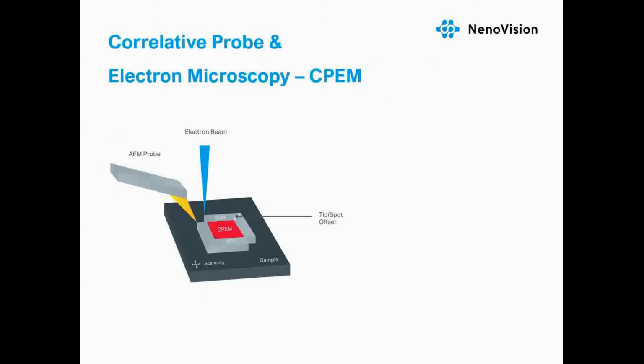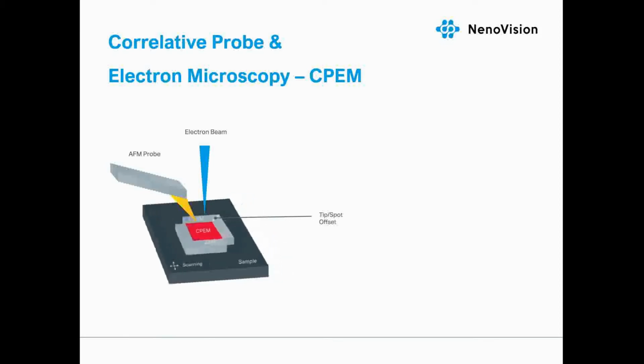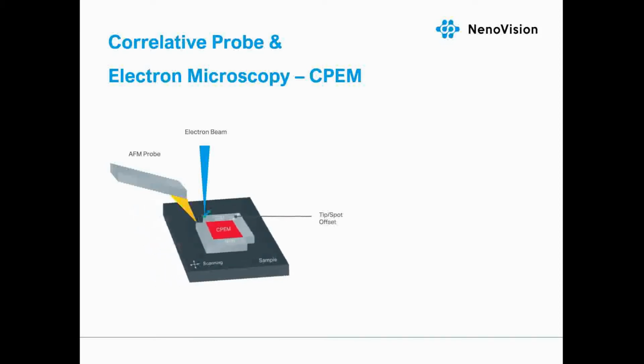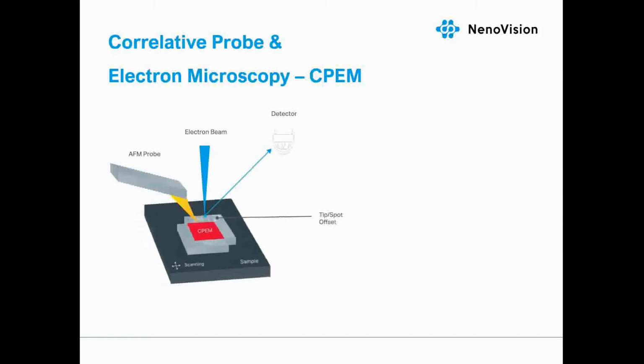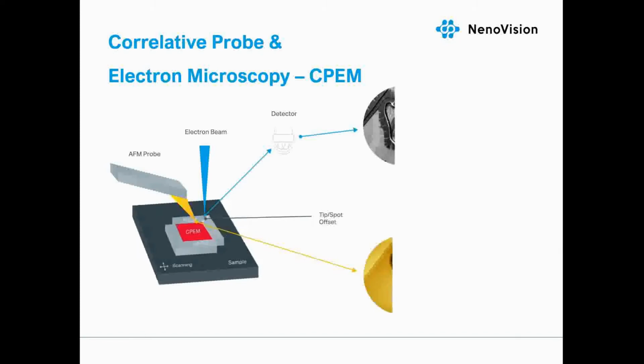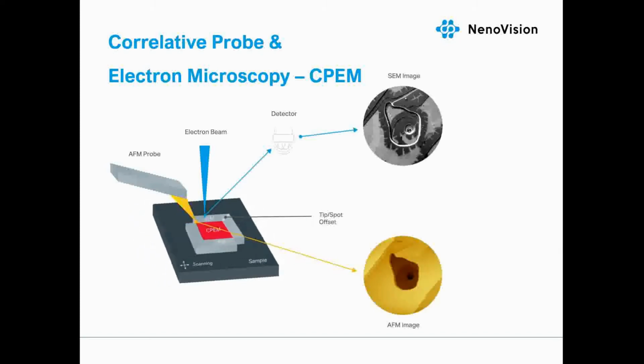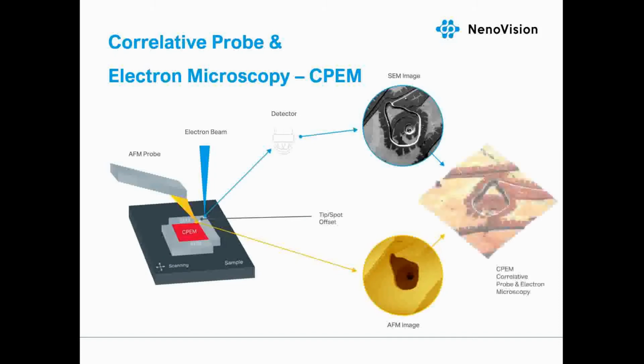CPEM stands for Correlative Probe and Electron Microscopy. This technology is unique to LiteScope and was developed for seamless data correlation. So let's have a look on how it actually works. On the sample, the electron beam points close to the AFM tip with a constant offset. And during scanning, the AFM tip and electron beam remain static. Sample is being scanned only by the LiteScope piezo scanner. And this enables simultaneous detection and acquisition of AFM and SEM signals at the same time, in the same place, and under the same conditions.